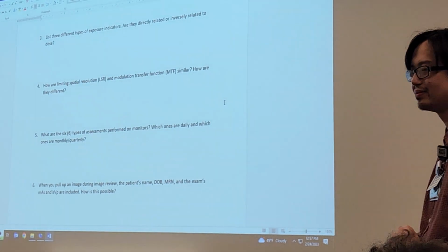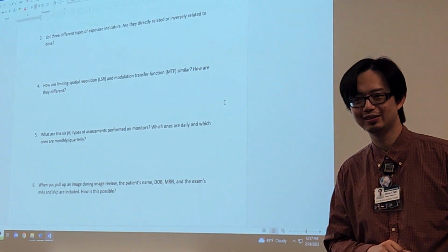Can I tell the difference? You want to tell the difference? Okay, sure, fine. Give me the difference. The difference is that LSR depends on outside factors and is less accurate compared to the MTF. All right. So yes, LSR does depend on outside factors, things like the monitor, things like whoever is trying to view those line bars, eyesight. So yes, LSR isn't going to be as accurate. It's not as consistent a measure when we want to describe.